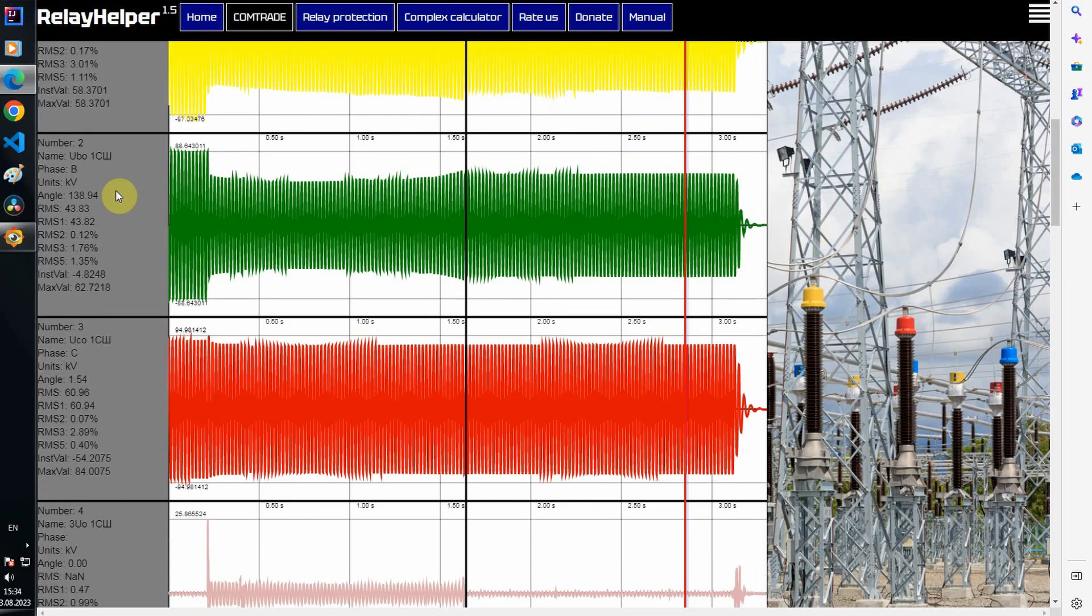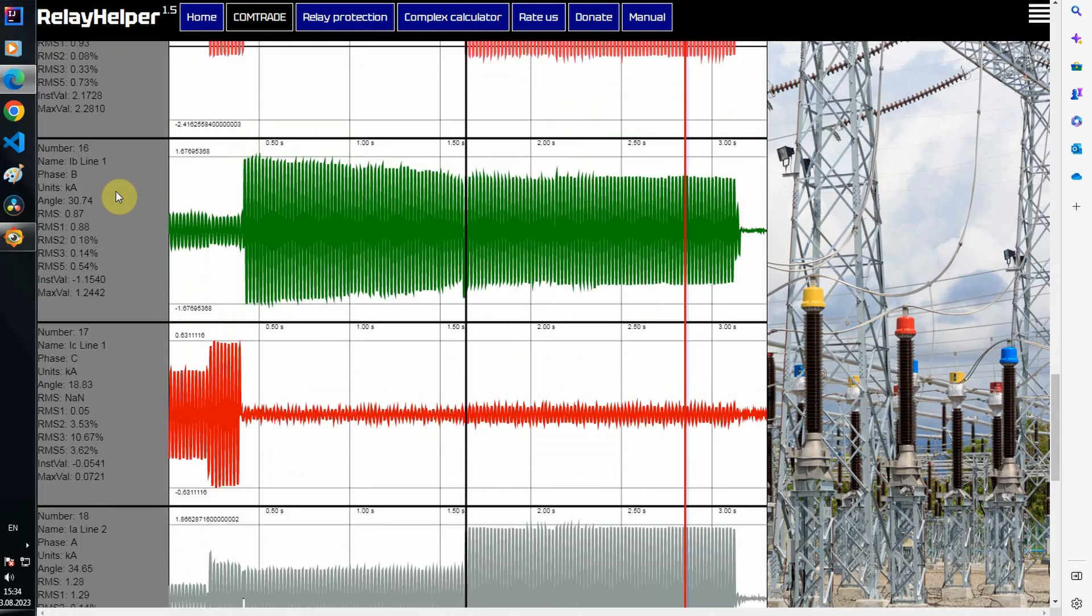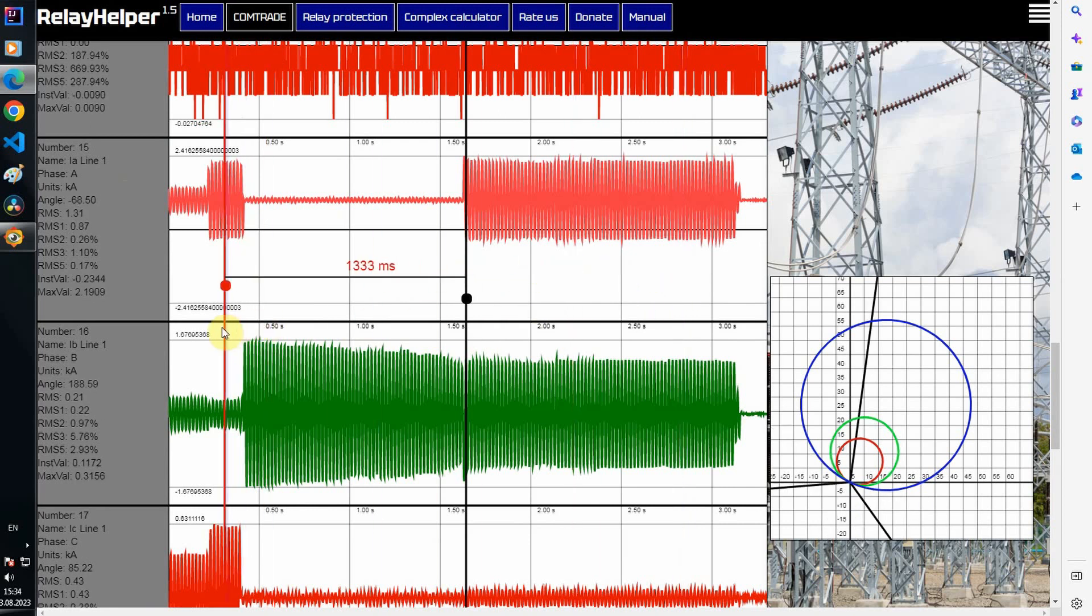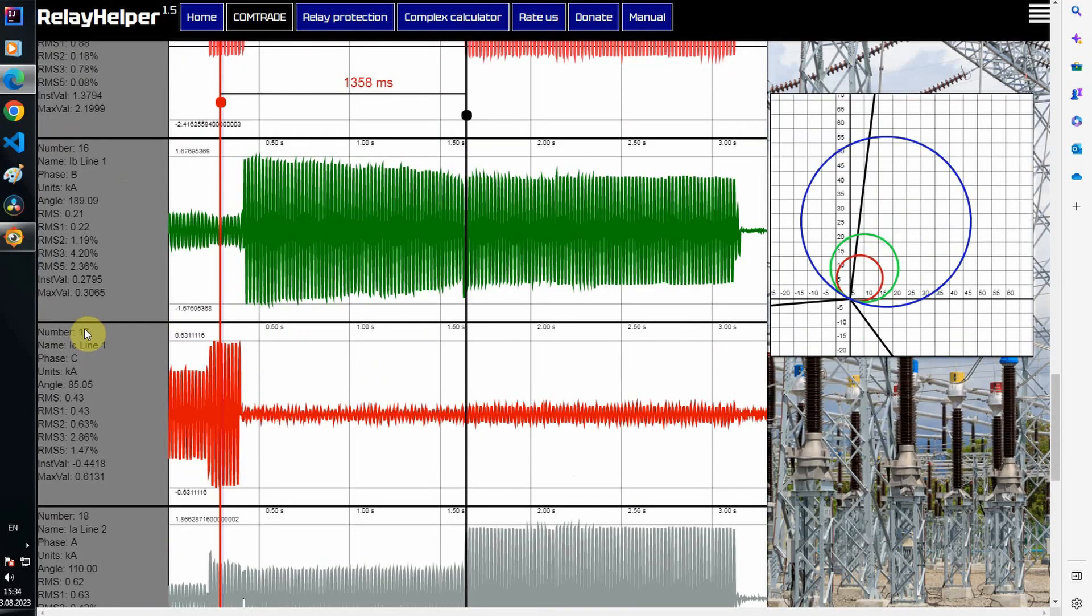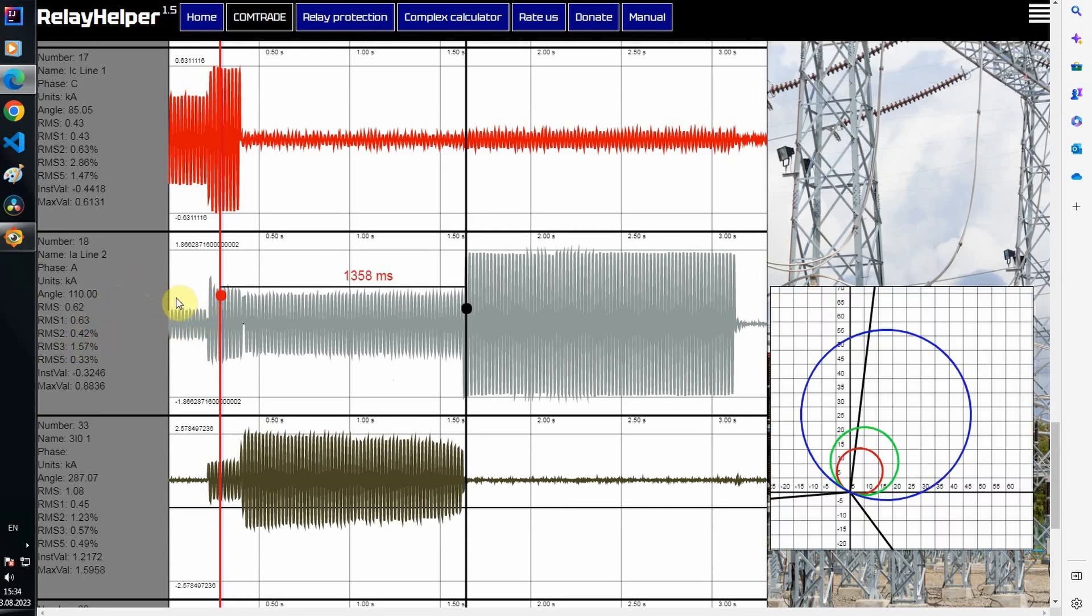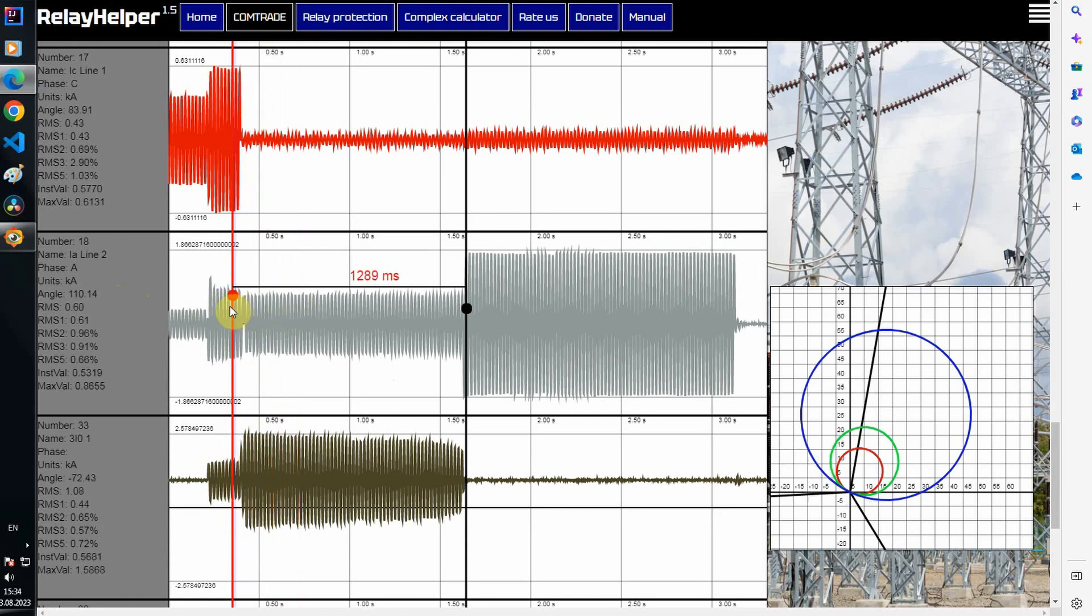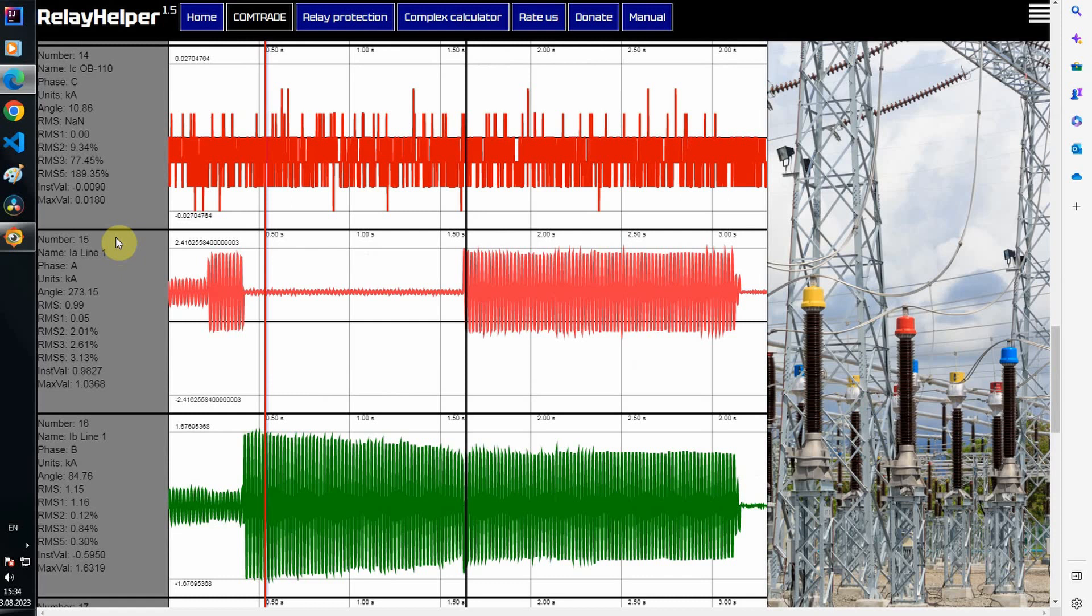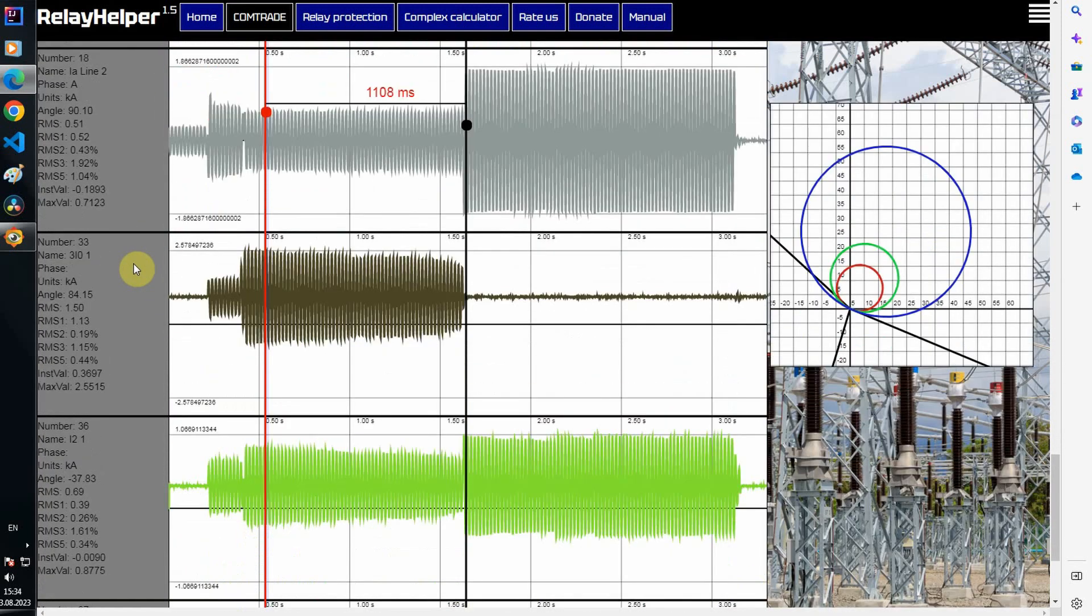To summarize, in this case we have a complex short circuit that goes from one type to another. The zero sequence current protections as part of the EPZ 1636 protection kit did not have time to work. The zero sequence current has stopped. The protections designed to eliminate phase-to-phase short circuits also did not have time to work, and a trip occurred at the power substation, as a result of which half of the city was left without electricity. Thank you for watching, peace for everyone.